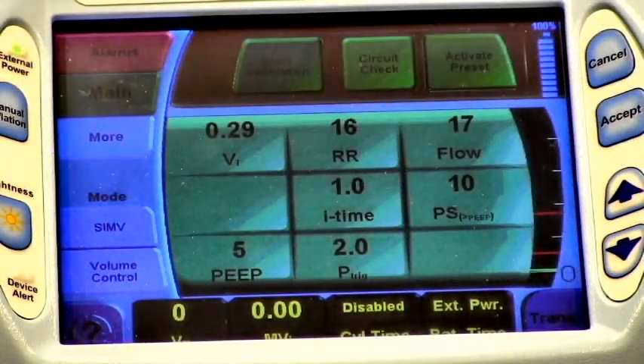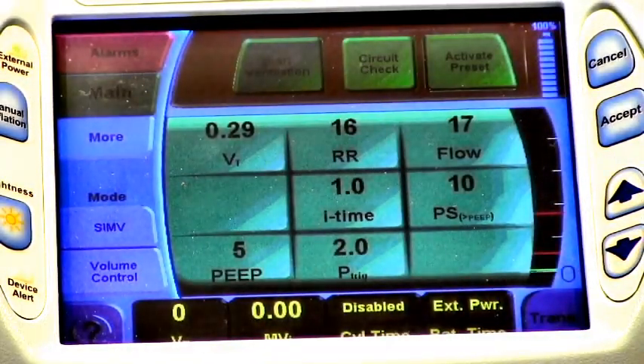Now we're going to focus in here on the screen itself. When the monitor first comes on and goes through its own internal checks prior to our circuit check, the screen that comes up is going to be all the ventilator settings based upon the last patient that it was used on. We obviously don't want to keep these settings for the current patient, so one of the things we talk about is getting your patient settings in here as early as possible. The first thing, however, we want to do is do our circuit check. That is important for every single patient. That ensures that the machine is set up and that the circuit is good. Everything is set up for this patient, and that the machine goes through its internal checks to make sure there's no problems.